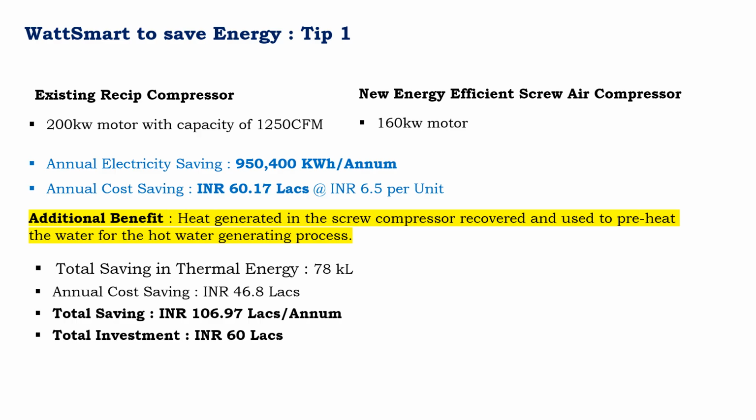And the investment for the upgradation was nearly 60 lakh rupees. So you can see the return on investment is even within 1 year. And this is the benefit of any intervention which somebody needs to make for any compressed air system, because the return on investment is much, much better. Compared to any investment in the stock market, here the IRR, internal rate of return, is nearly 40%. So better returns, and the reliability is also improved, because the recip has more operational and maintenance issues, while the screw is much more reliable.